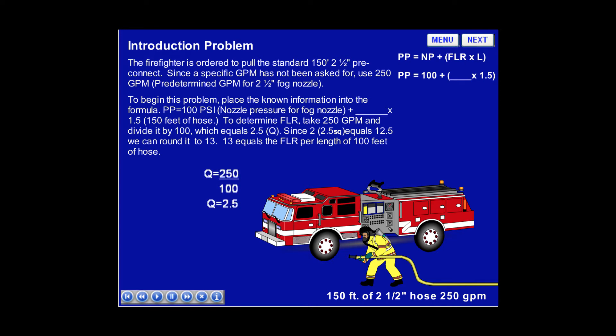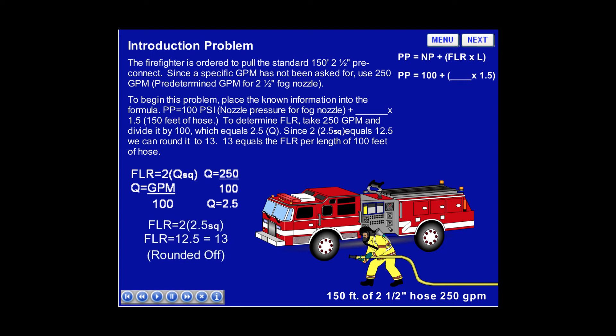To determine the FLR, take 250 GPM and divide it by 100, which equals 2.5 for Q. Since 2 times 2.5 squared equals 12.5, we can round it to 13. 13 equals the friction loss rate per 100 feet of hose.